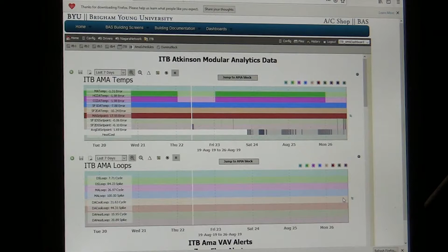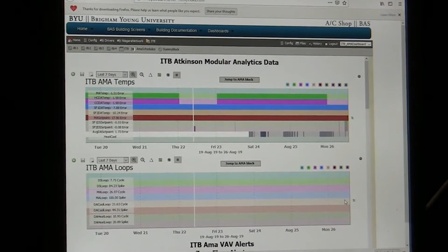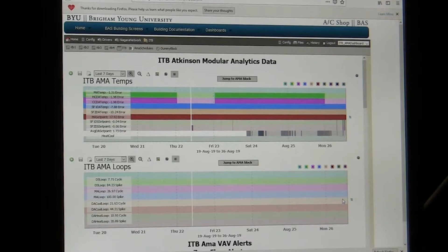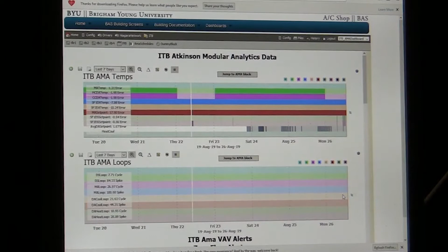Typically, you'll add or subtract a slight offset from the sensor to get it to calibrate correctly. So on 2 of our buildings now, we have analytics. And we've done some analytics on several other buildings that are quite a bit more. But these are the Atkinson analytics that give us kind of a functional test of the system on a periodic basis. So the air handler, we're testing, I don't remember if it's once a week or once a month. We do just what we've done. We put it into a full return air, run it for 20 minutes or so, half an hour, and then we check all the sensors and how close they are to each other. Then once they've done that, there's a report that comes, and if these lines are bright, that means that we were outside of the 2-degree margin that we set as our error. So if we're within 2 degrees all the way through, we say, yeah, we're pretty close, we're going to leave it alone. But if it's not, it lets us know that we have an error and that we need to probably go and look at those and calibrate them or verify what's going on.